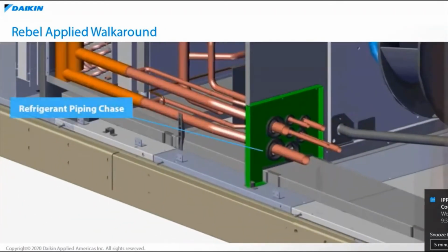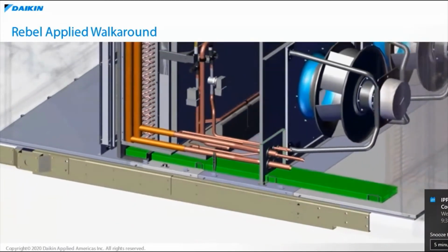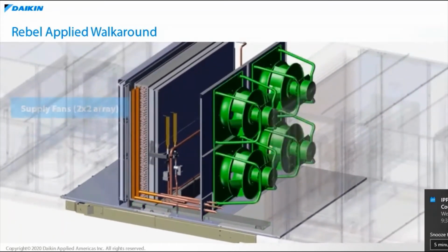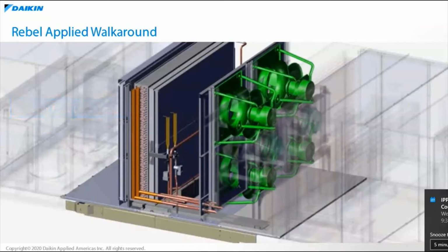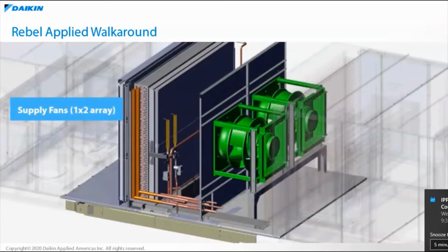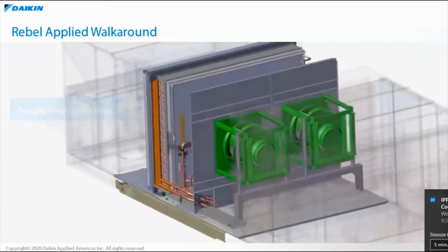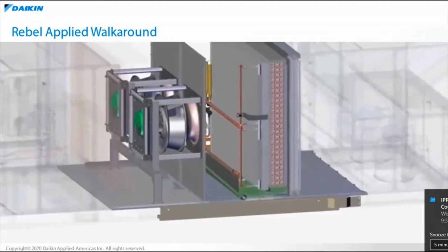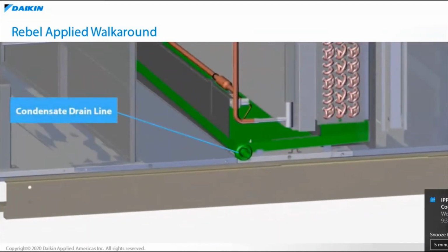A refrigerant piping chase runs along the control or right side of the unit, providing access to piping, as well as an electrical wiring chase housing both power and controls wiring. In the supply air section are the supply fans. All supply fan combinations are part of a fan wall. Shown here is a 2x2 fan array. Depending on unit size and configuration, you might also see a 1x2 fan array. On the left or non-control side of the unit is a condensate drain line, allowing removal of condensate from the evaporator coil.